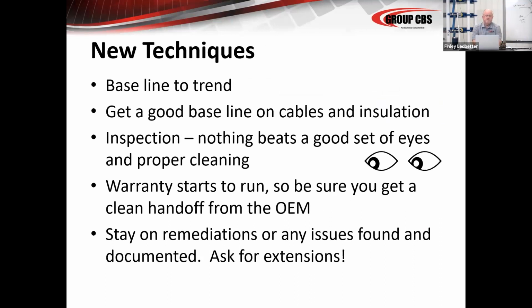So you want a credible test. You want all the electrical tests, all the manufacturer's recommended mechanical tests. You want a baseline. You want to know that the day you installed the equipment and you energized it to begin to pass power into your system to go into commercial operation, that equipment operated successfully, that you have ultimate confidence in its reliability. Then the length of the maintenance cycle to where you're going to start maintenance testing comes into play. So it's reliable the day one it's turned over because you've done all the work. You've done the mechanical tests, you've done the electrical tests, you've done the inspections, you've turned it on, IR testing, you've done everything you should do, everything you can do. Now the warranty starts to run.